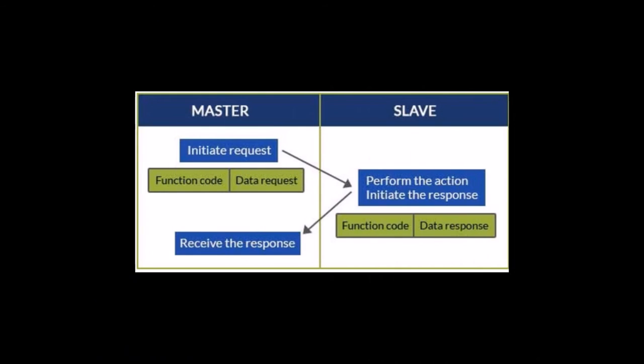A little in-depth on how the master and slave work on Modbus communications. First of all, the master will initiate a request by sending the function code and the data request such as the starting address and the number of registers needed along with slave IDs, in which the corresponding slave will respond by performing the actions and sending the response to the master.